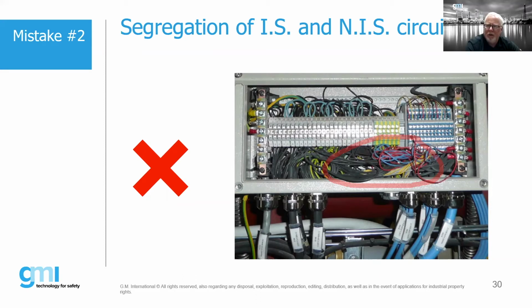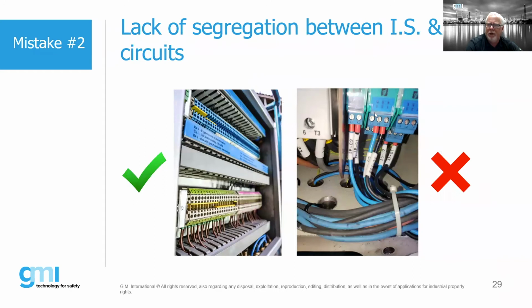Absolutely, absolutely. It's mandatory, it's an absolute requirement. And as GMI, we are designers of products. It's a limitation we have. When we design, we always have to keep 50 millimeters between anything, even in the design of the circuit itself. That's right. And people ask sometimes why barriers are designed, or at least the distance between the incoming and outgoing. I think we may be able to show it here, at least partially. This distance here between the outgoing and the incoming has to meet a minimum requirement.